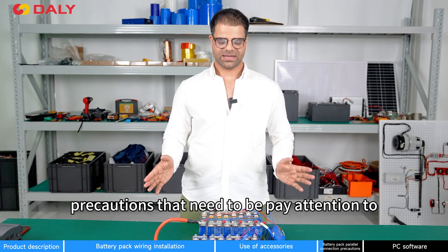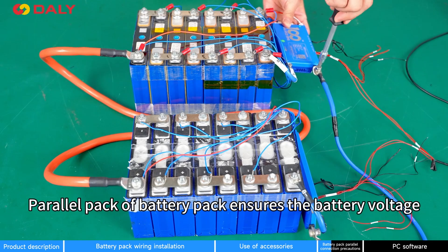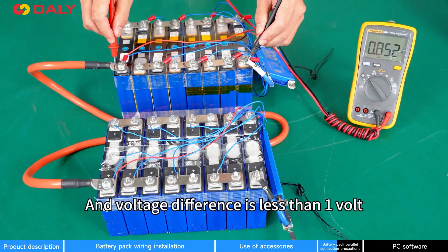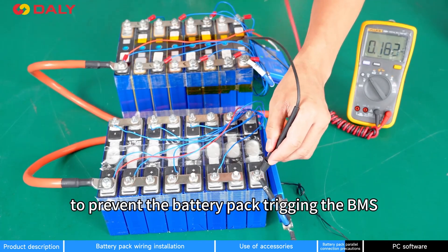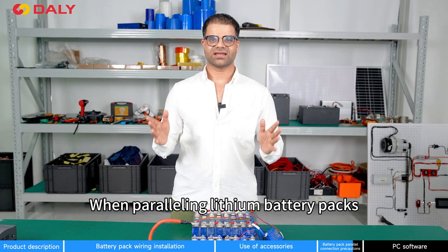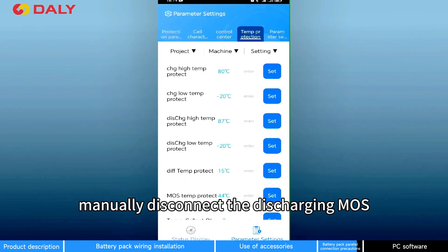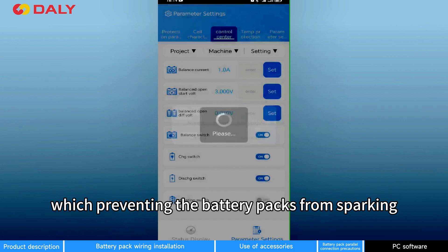Precautions to pay attention to when batteries are parallel connected: the function of the parallel module is to ensure the voltage is the same in each battery pack, and the voltage difference is less than 1V, to prevent the battery pack from triggering the BMS short circuit protection by high current. When batteries are parallel connected, manually disconnect the discharge MOSFET in the Bluetooth app or PC software, which will prevent the battery pack from sparking.